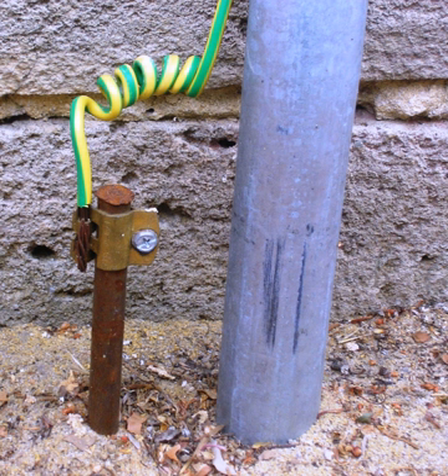On an HRG system, a sensing resistor is used to continuously monitor system continuity. If an open circuit is detected, e.g., due to a broken weld on the NGR, the monitoring device will sense voltage through the sensing resistor and trip the breaker. Without a sensing resistor, the system could continue to operate without ground protection, since an open circuit condition would mask the ground fault and transient overvoltages could occur.